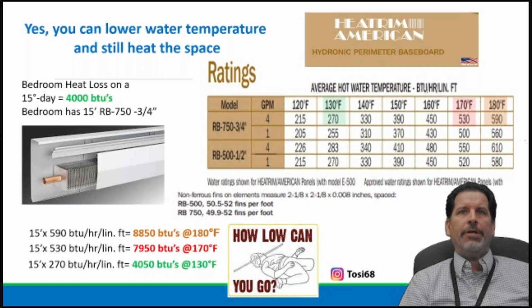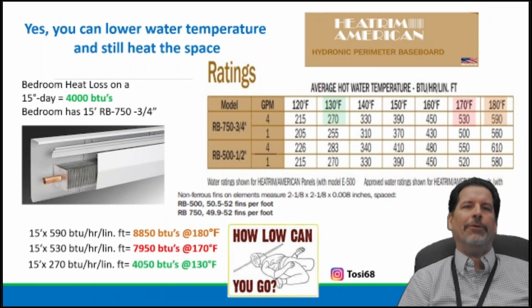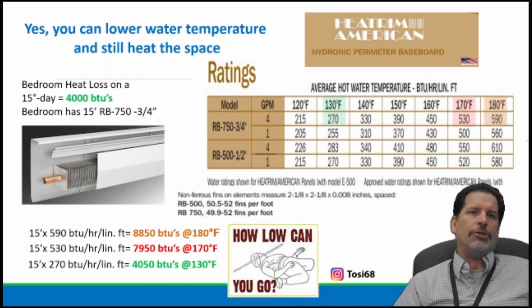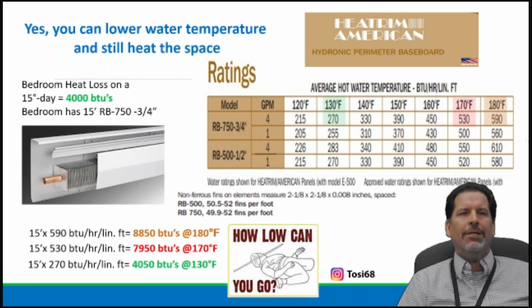It's an average hot water delivered, right? Hot water temperature. So at 180, every foot of element is 590 BTUs. That's almost 8,900 BTUs for a room that only needs 4,000. We want to lower water temperature. Lowering water temperature, you'll see, gets us higher efficiencies. Average water temperature now, okay, we're starting at 180, but really the average around the whole system, if you want to get a little closer, is roughly 170 degrees, right? We go out at 180, we come back at 160. There's our 20-degree delta T. So we split it, take the middle.